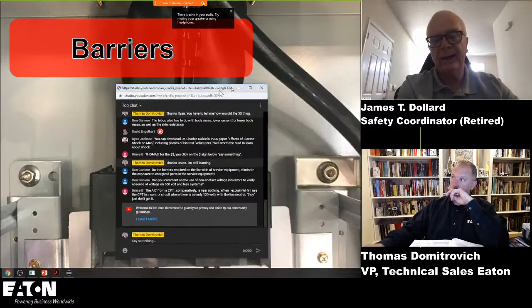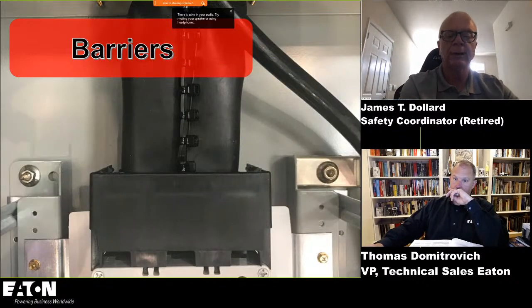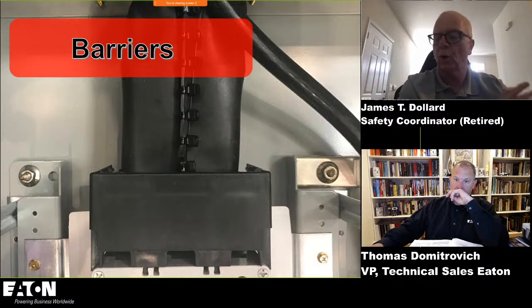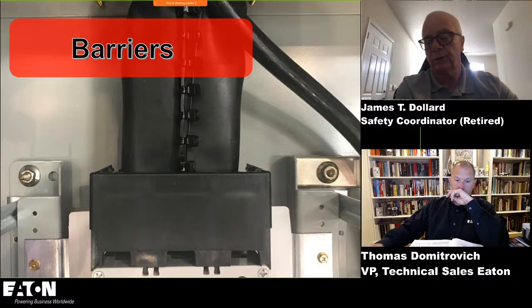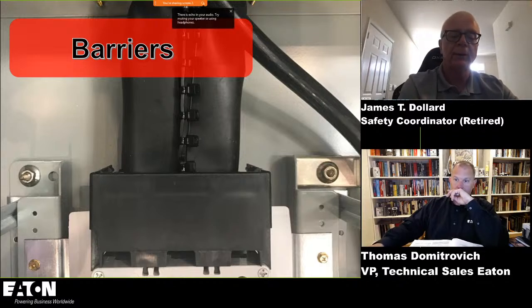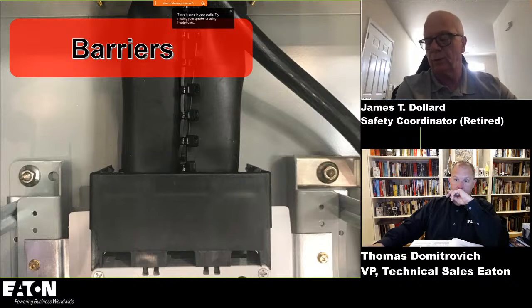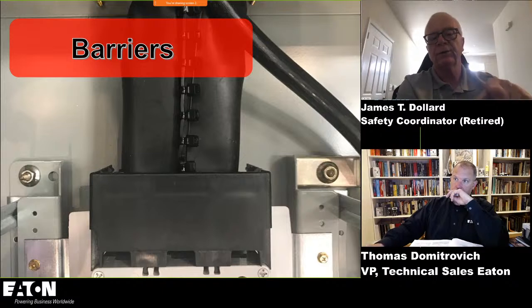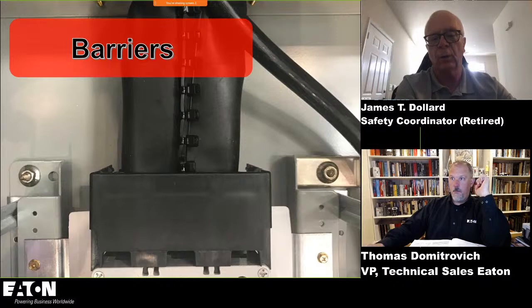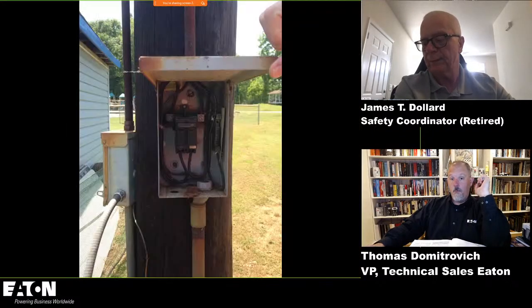So the same holds true for barriers. Now, these barriers aren't all created equal. I have seen some, and I'm sure Don Ganir has seen them as well, that are extremely robust and do a fantastic job of actually eliminating any potential. And when I say any potential, the most likely would be something like a metal fish tape, which we shouldn't be using in this situation anyway. If we needed a fish tape, it should be non-conductive. But others aren't so tight, because the UL standard for inadvertent protection wouldn't necessarily require what we see on the screen. This manufacturer went a step above. So the bottom line is the employer is going to have to make that determination. You're going to have to dress when you open that equipment because you don't know if there's a barrier there. And then you're going to have to make a determination if there are exposed energized conductors or circuit parts.